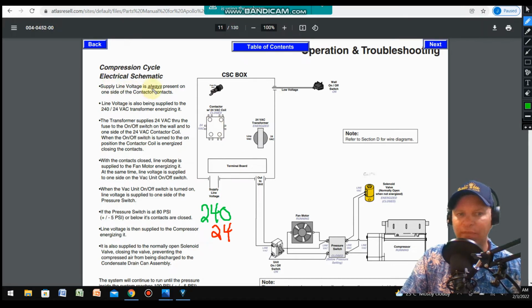The supply line voltage is always present on one side of the contactor contacts. So we have supply voltage coming in. It goes here to these two contacts. Now you can imagine these contacts as being almost like parallel bars going through here, except they're open right now. They will be closed when the contactor is activated, so basically this opens and closes.